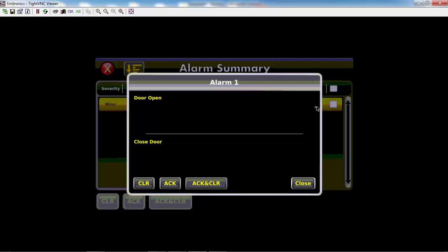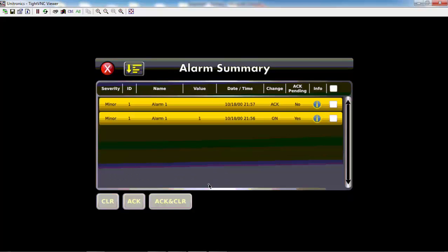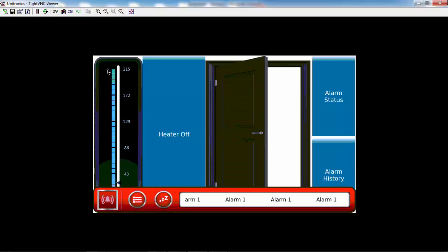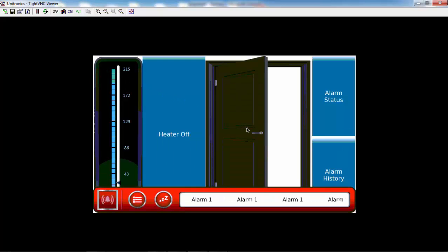You'll notice that if I try to acknowledge and clear, we see now that there is a new entry that says that we have acknowledged the alarm. However, the alarm has not yet been cleared because the trigger condition, or the door being open on screen, is still active. To totally clear this alarm list, we must resolve the trigger condition by closing our door on screen.